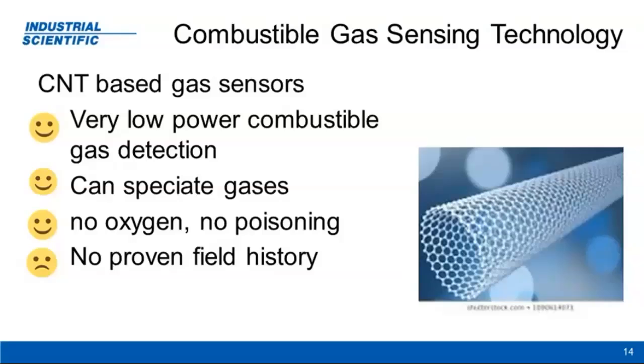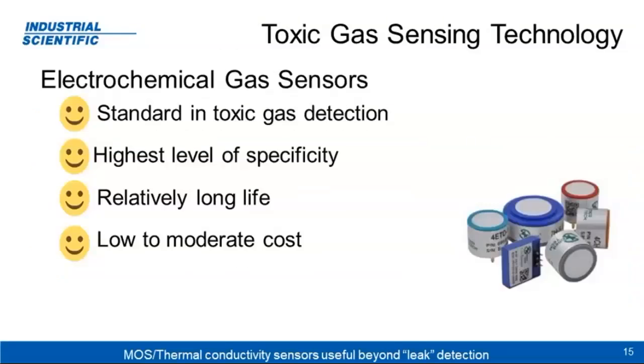They have the potential to speciate gases if they're set up properly, and because they're very small, it's easy to build an array of sensors, maybe even hundreds, that can all be characterized differently and really allow you to speciate a gas. Typically no oxygen, no poisoning. But while there's a lot of research being done in carbon nanotube-based sensors, there's no sensor that has really been commercially successful on the market yet to a large degree, and these sensors have no proven field history. So while the technology is very promising, and I think the future of combustible gas detection lies in this technology, it's certainly not there yet.